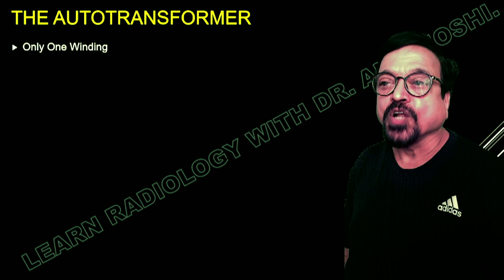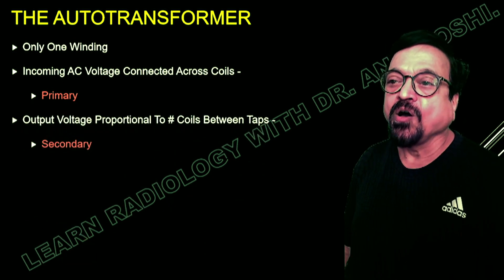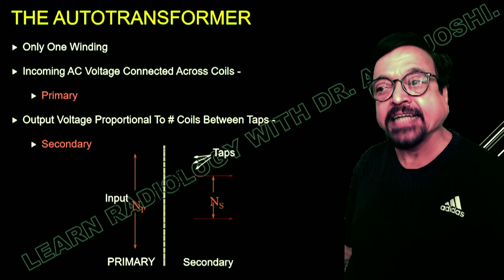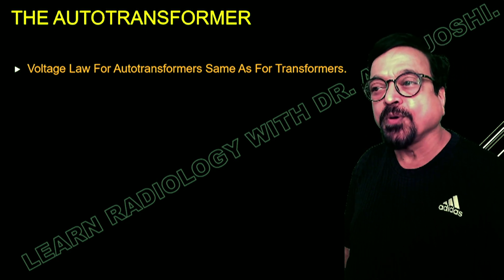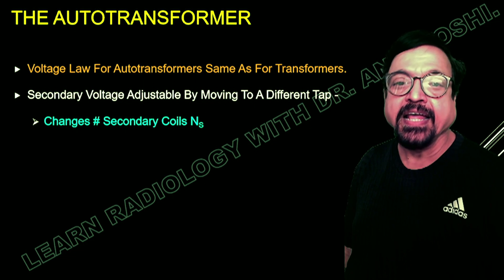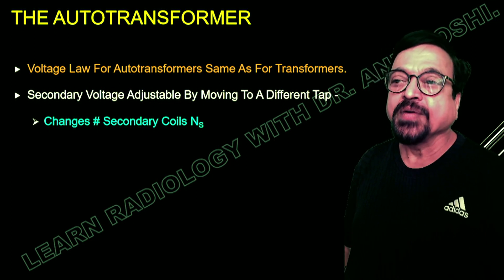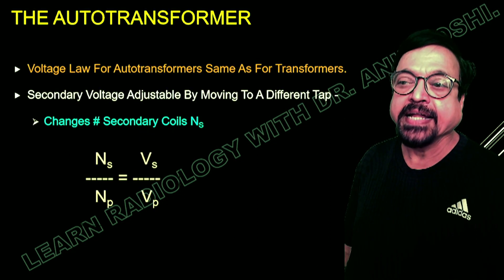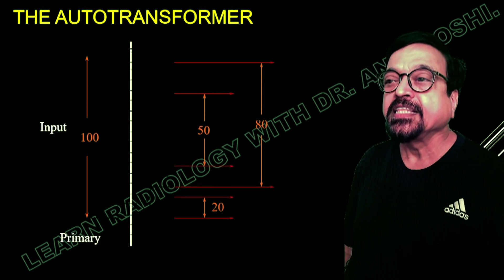This flux links with all the turns forming the coil, inducing voltage into the secondary turns. In an auto transformer there is only one winding, with the incoming AC voltage connected across the coils as the primary. The output voltage is proportional to the coils between the taps, which give different voltage levels acting as the secondary. The voltage law for an auto transformer is the same as for other transformers; secondary voltage is adjustable by moving to a different tap — a sliding tap is provided. You can see the adjustable taps when examining the machine.